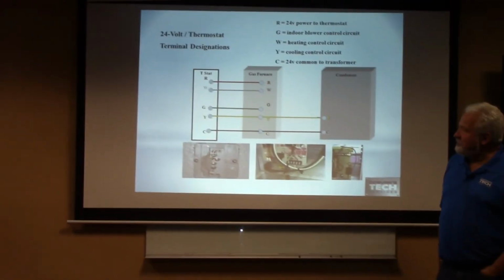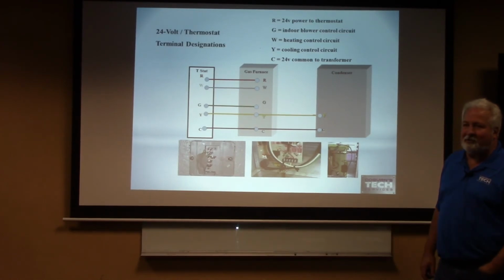Does that make sense? What we're going to do is shift our world now. We're going to go back to something a little more practical, something you guys see on a regular basis. Now, I wrote this class for a technician who does not have any idea about anything, so we're going to go right to the beginning and say R is going to be your 24-volt power. That's going to be your voltage applied. G is going to be your indoor blower motor circuit. Your W is going to be your heating control circuit. Y is going to be your cooling circuit. And your C is going to be the other side of your potential. That's going to be your neutral potential, if you will. That'll be the 24-volt common.